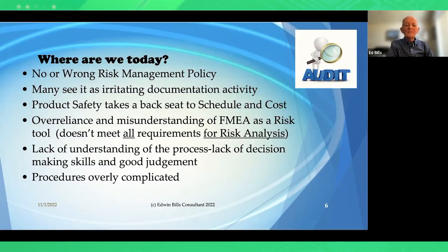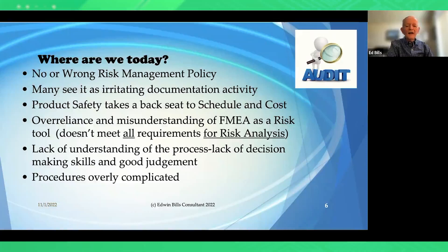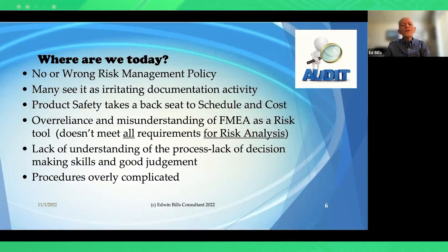Many see risk management as an irritating documentation activity, but it is not. Product safety often takes a backseat to scheduling and costs. There is an over-reliance and misunderstanding of FMEA as a risk tool — it is not risk analysis, but it is a tool to establish fault conditions in products. If the fault condition effect is related to safety, it leads to a hazard, and that is where risk analysis starts: after FMEA. There is also a lack of understanding of the process and a lack of decision-making skills and good judgment.